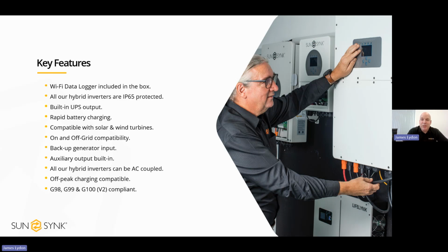Rapid battery charging. The maximum power you can put into the batteries and take out of the batteries is the rated value of the inverter. Some other manufacturers, if they've got a 5 kilowatt inverter, might restrict the charge and discharge to the connected batteries to, let's say, 3 kilowatt. But with Sunsynk, it's always the rated value of the inverter.